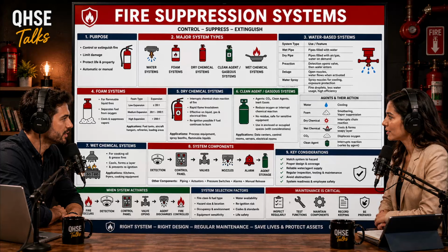That is a fantastic question. The answer cuts right to the heart of fire dynamics. First, no. OSHA emphatically does not want untrained employees fighting fires. If an employer expects employees to use extinguishers, they must provide hands-on training annually. If they don't, the policy must be evacuate immediately. Okay, so assuming they are trained, why the strict 100-foot rule?